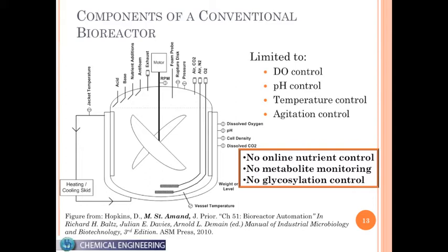Quick comment there. I thought early on we might have a small problem there. Yep. When she said offline before, offline means they produce the product, then pull a sample, go off someplace else and test it, and then come back and say whether it's any good or not. Not the best setup. An online control would be, we're making it now, we can sample right while we're making it, test it, and then adjust our process to fix it if it needs fixed. Right. That's the difference between offline and online. So you have no time lags. You don't make a bad batch. You fix it while you're making it so it doesn't get bad.